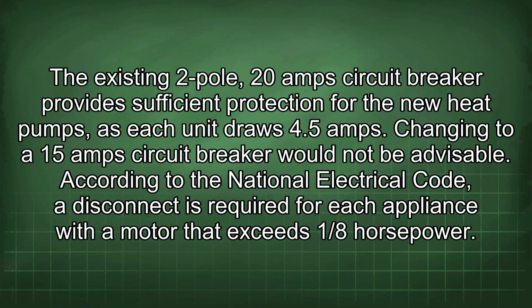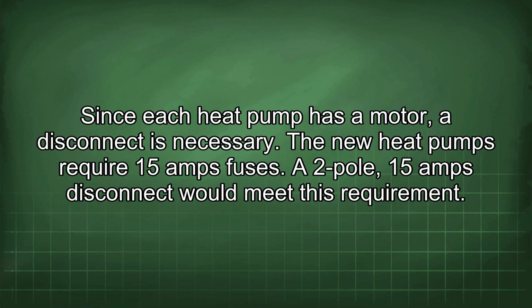According to the National Electrical Code, a disconnect is required for each appliance with a motor that exceeds 1/8 horsepower. Since each heat pump has a motor, a disconnect is necessary. The new heat pumps require 15 amps fuses. A 2-pole 15 amps disconnect would meet this requirement.